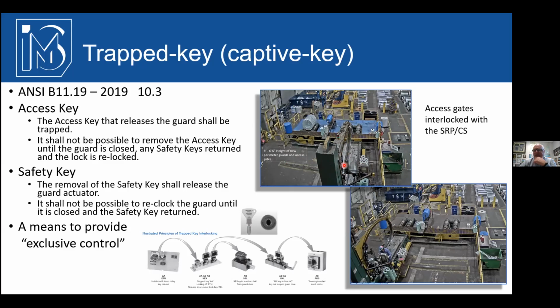Really no means of detecting a human in there. If somebody's in there and this machine's going through its sequence, it's going to continue to go through its sequence regardless of what happens to the human. The other thing that happens is sometimes these coils don't get seated properly on these rolls, and they walk off and go smashing through the floor or smash right on top of somebody. So this company wanted to ensure that there was nobody inside this perimeter.